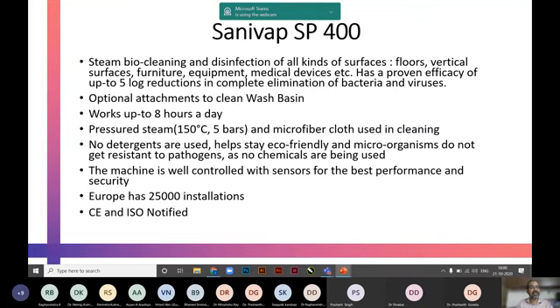It can even be used for more than that, but the recommended time is 8 hours. It works at 150 degrees centigrade and 5 bars pressure, so disinfection becomes almost complete, and it doesn't require any kind of chemicals. That is one advantage, and the housekeeping job becomes easy and high tech.